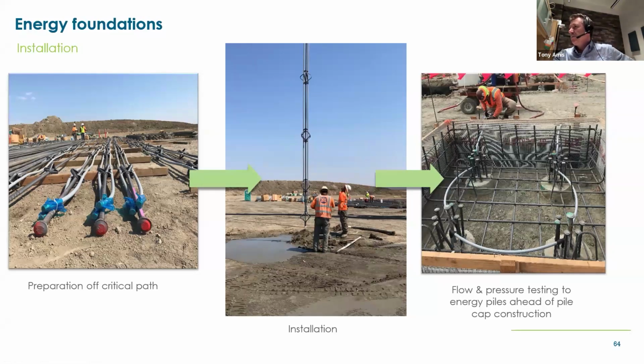So what you see here is the geothermal loops simply attached off of the critical path, and the piling contractor was allowed to just carry on as normal. The other benefit of this particular project was that the ground conditions were highly contaminated, and they were looking at a geothermal borehole solution anyway - about 500 feet of boreholes were to be drilled. The problem was they were going to generate an enormous amount of contaminated spoil to be removed from site, and they were also concerned about dragging contamination down into lower aquifers.